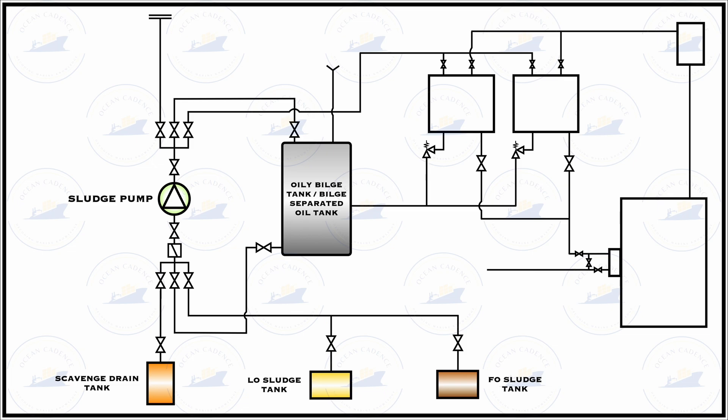The lube oil sludge tank would have a richer mixture, and running the incinerator on lube oil sludge tank content purely would give higher temperatures. The scavenge drain tanks also receive a daily amount of generation from the main engine. The BSOT is a unique tank that mostly has inlets from different collection points and save-all trays on board. For example, if a pump in the fuel oil section leaks, the oil collected in the save-all tray and naturally drained would flow through the save-all tray collection into the BSOT.